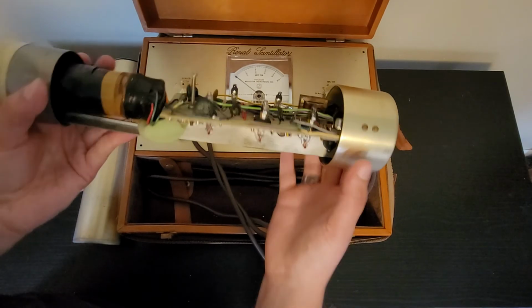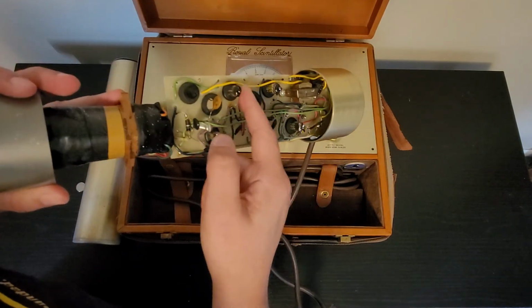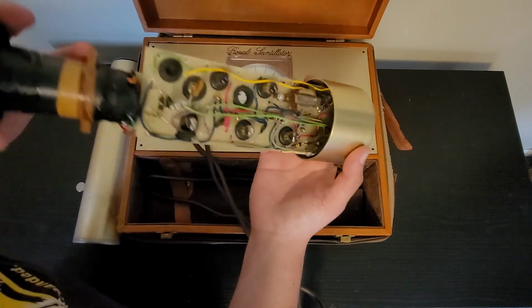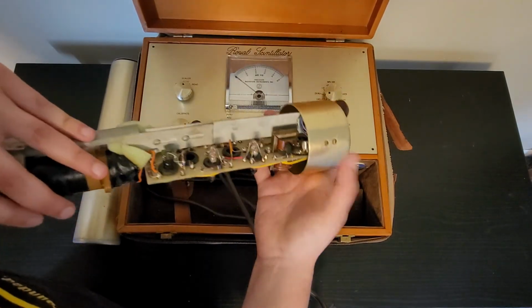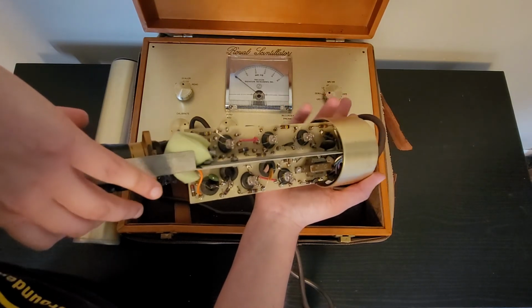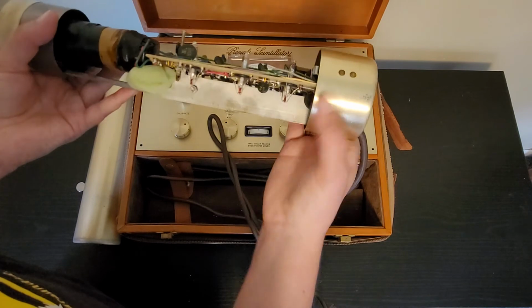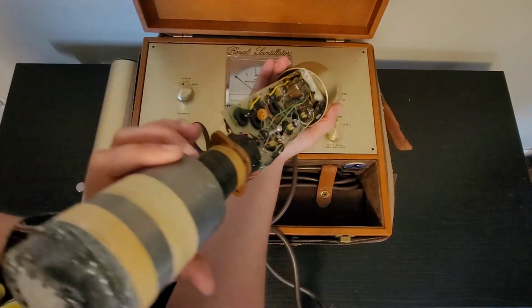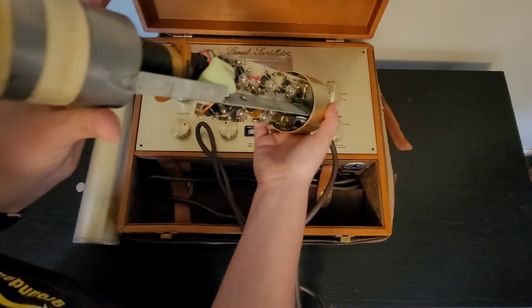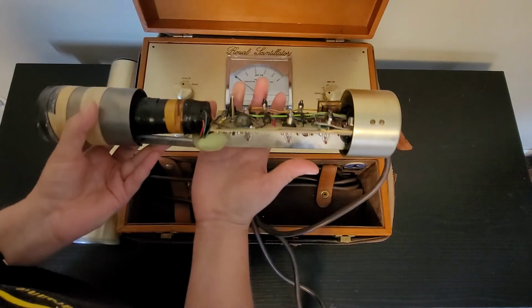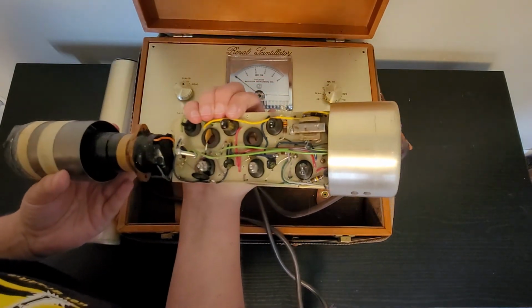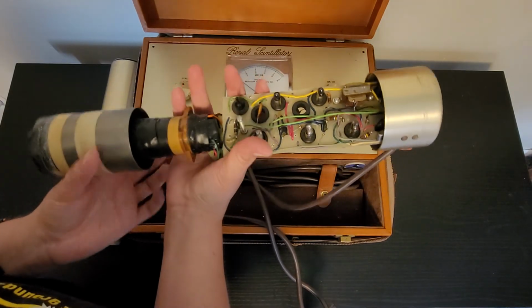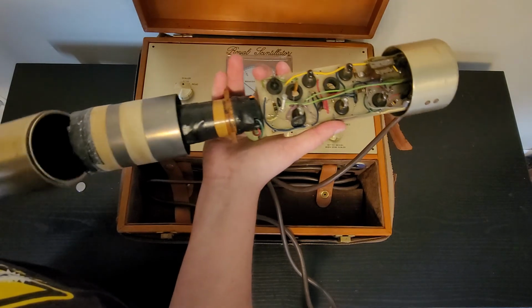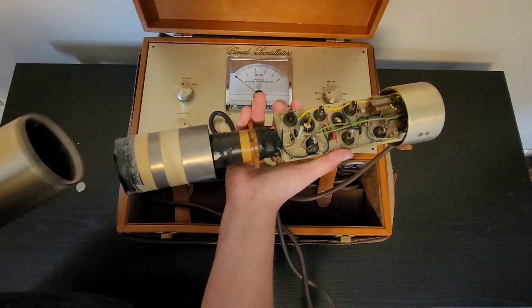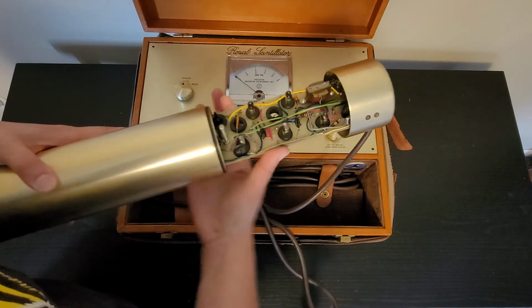So on the board here, we have a lot of these little tiny baby tubes. I believe they were used in military applications. A couple of little tiny transformers. There's a big circuit board, all fitting inside that probe, and that's why the probe is so much bigger than most scintillation detector probes. I haven't had to work on this yet, but if I do, that's where a lot of the electronics are. And then of course there's an O-ring on here to seal this, and this just fits back together.